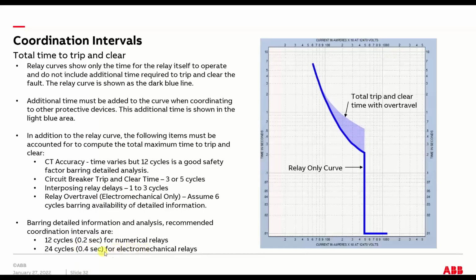And here's a couple really, really rough recommended intervals. If you're looking at an electromechanical relay and you didn't have detailed information, a safe number to use for the time interval between devices was about 0.4 seconds. For a numerical relay, you can cut that at least in half to 0.2, and most of the time you can go much lower than that, to probably no less than 0.1 second or 6 cycles. That's probably cutting it to the bone. But you can get tighter coordination as long as you put the work in of doing the engineering analysis, because there's a lot to it.